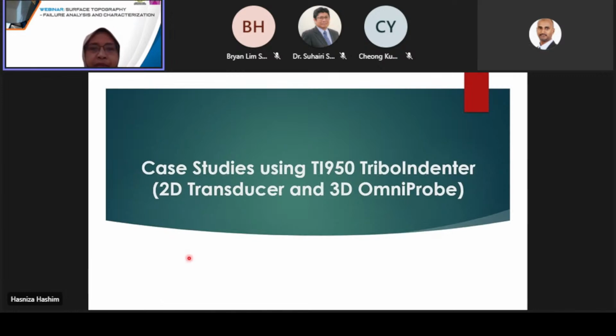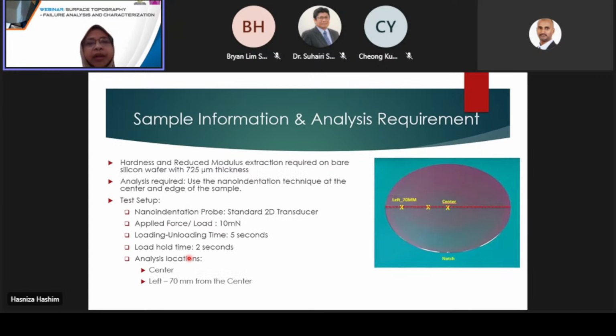Now, I would like to show you some case studies using our TI 950 TriboIndenter. We are using two types of probe, which are the 2D transducer and the 3D OmniProbe. The objective of this testing is to extract the hardness and modulus from the silicon wafer. The analysis requires indentation at the center and the edge of the sample, so we are using the 2D transducer probe. We apply a force of 10 millinewton with a loading and unloading segment time of 5 seconds and a hold time of 2 seconds.